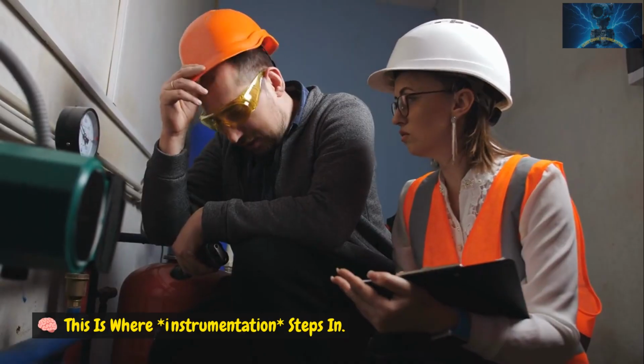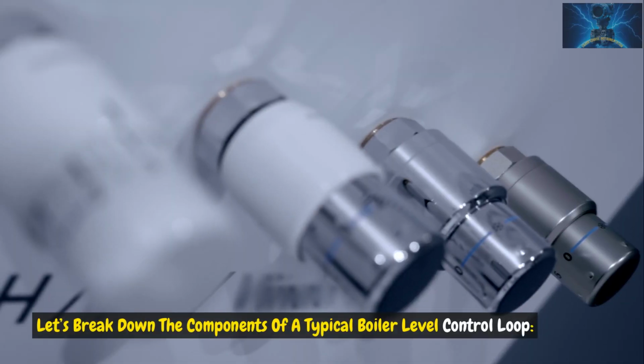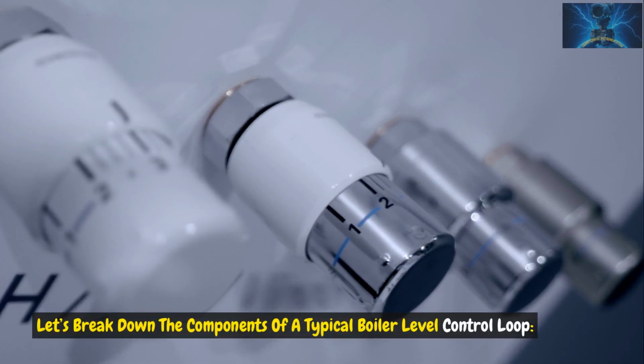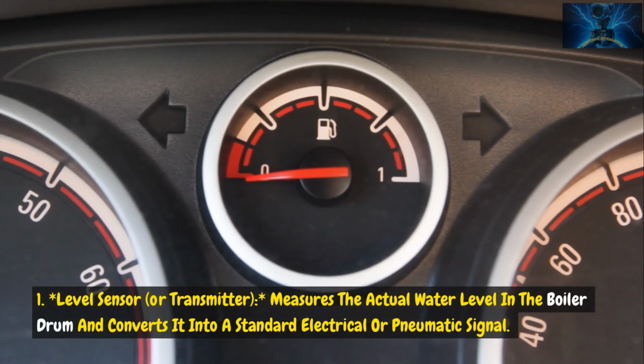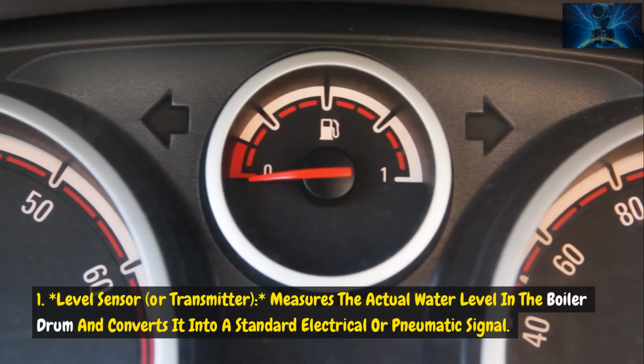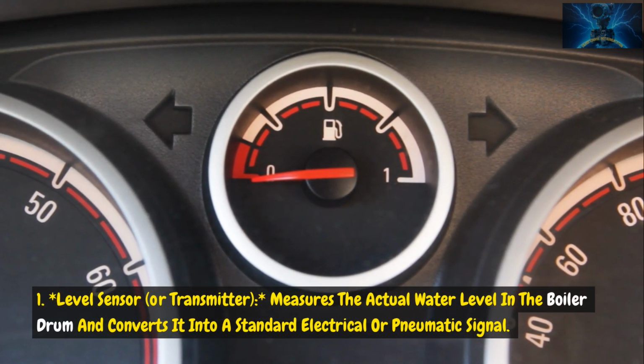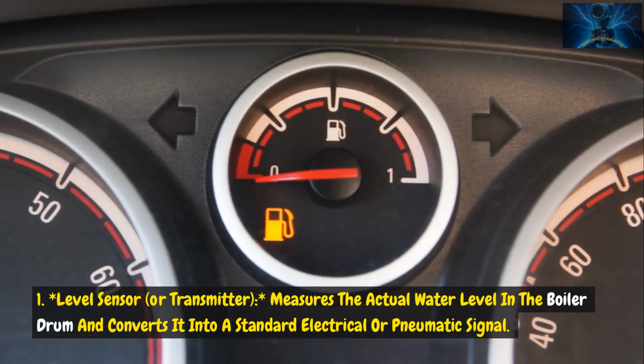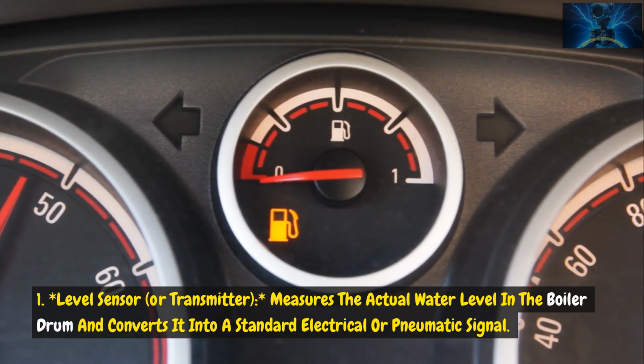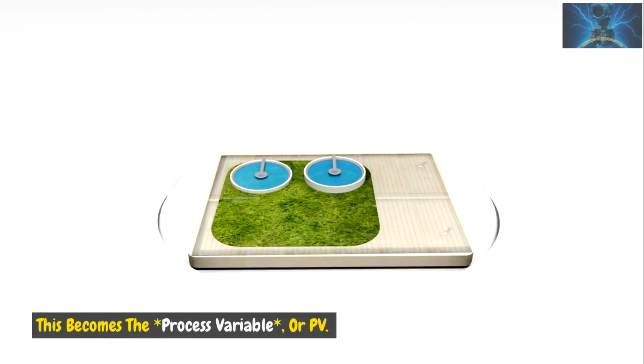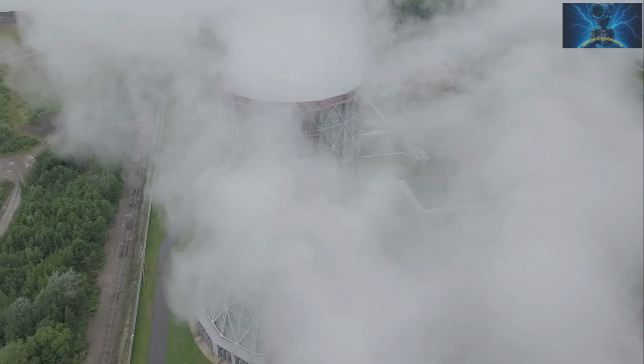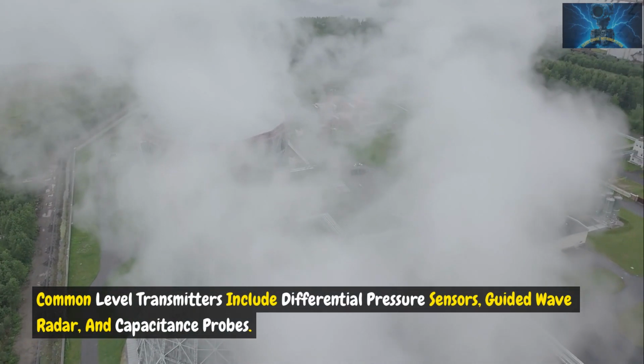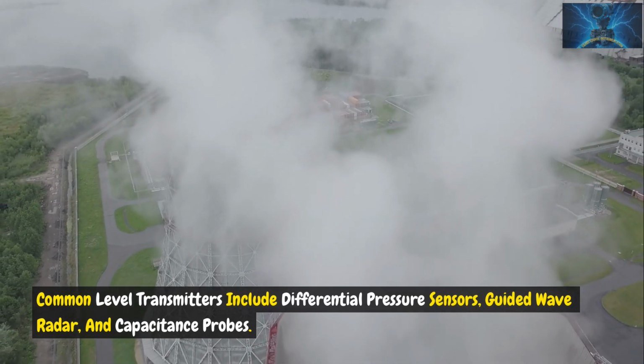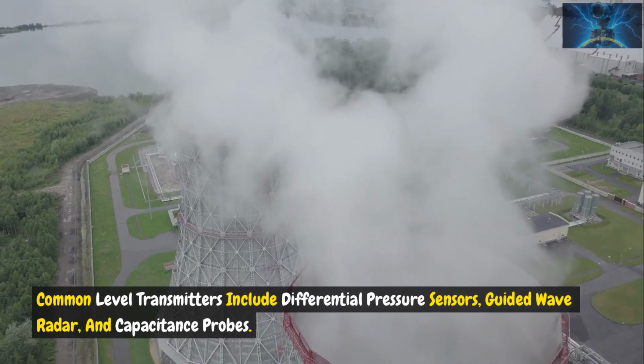This is where instrumentation steps in. Let's break down the components of a typical boiler level control loop. 1. Level sensor, or transmitter. Measures the actual water level in the boiler drum and converts it into a standard electrical or pneumatic signal. This becomes the process variable, or PV. Common level transmitters include differential pressure sensors, guided wave radar, and capacitance probes.